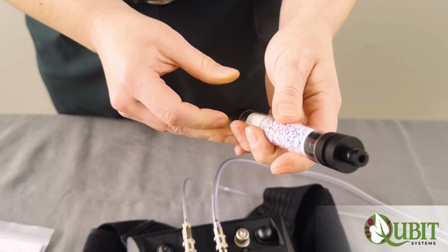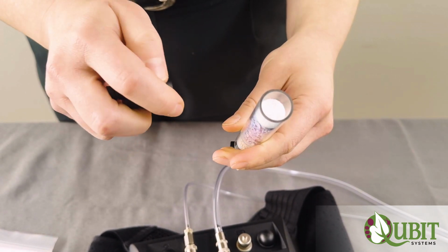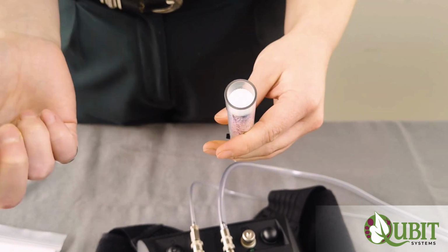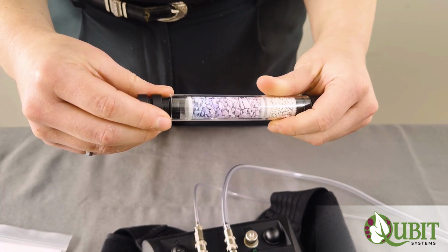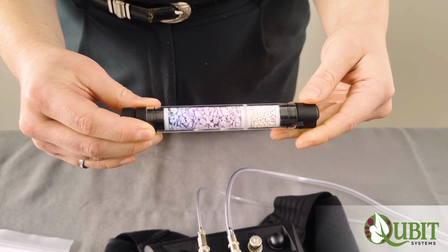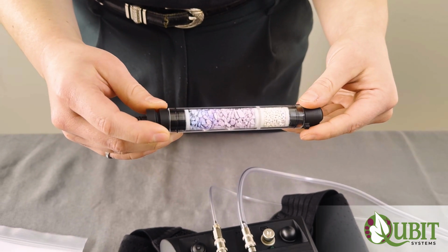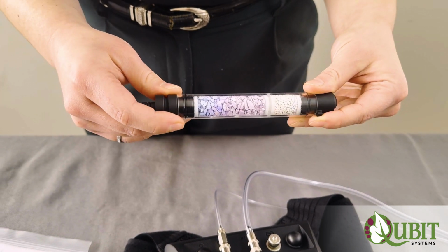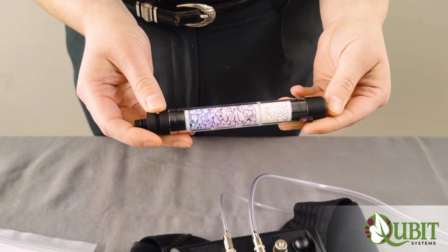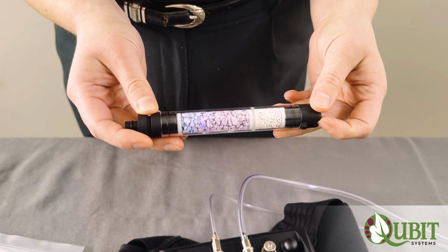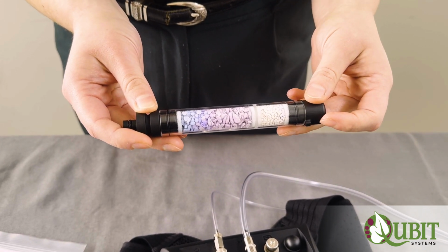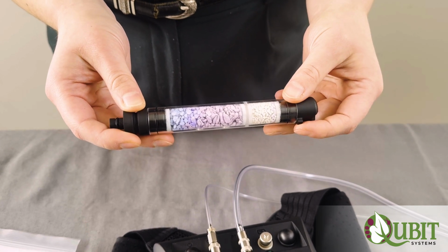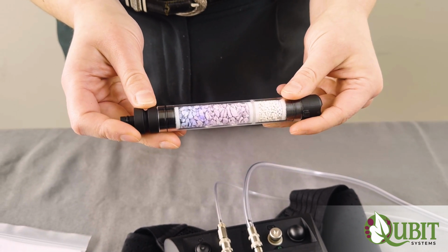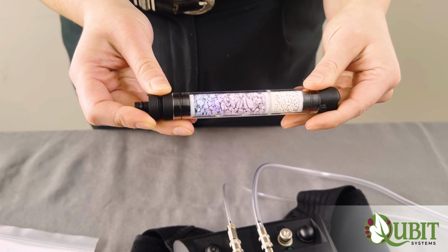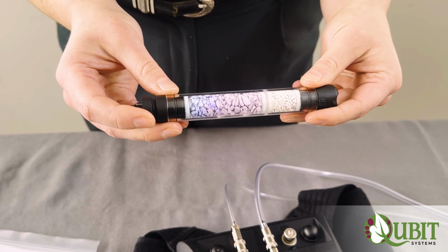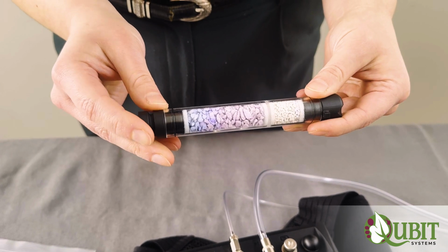To replace the Drierite, similarly, you would remove this volume of Drierite after the filter and place it aside. A nice thing about Drierite is that you can regenerate it, removing the moisture from the chemical, by placing it on a baking sheet and putting that baking sheet in the oven for 1 hour at 210 degrees Celsius. After regenerating the Drierite, the chemical will appear a pale blue, sort of periwinkle color, and as that regenerated Drierite expires, it will turn a very pale pink color.